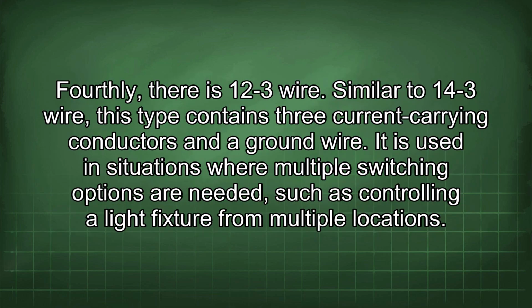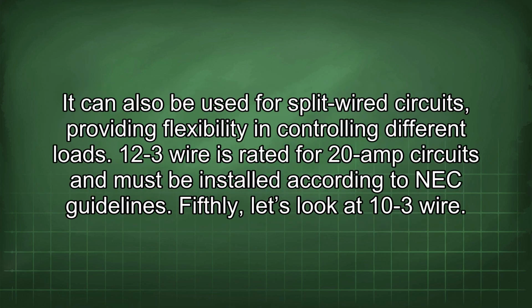Fourthly, there is 12-3 wire. Similar to 14-3 wire, this type contains three current-carrying conductors and a ground wire. It is used in situations where multiple switching options are needed, such as controlling a light fixture from multiple locations. It can also be used for split-wired circuits, providing flexibility in controlling different loads. 12-3 wire is rated for 20 amp circuits and must be installed according to NEC guidelines.